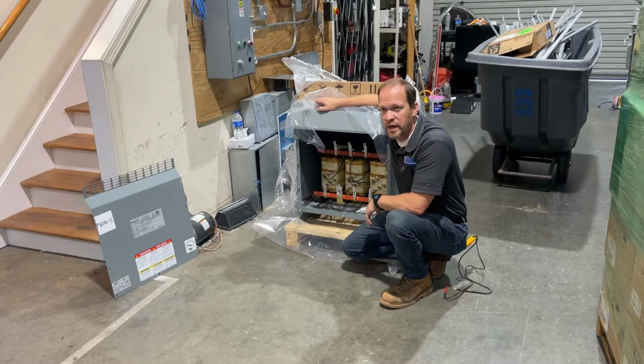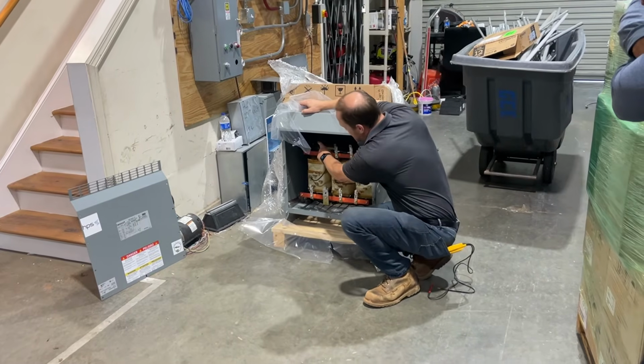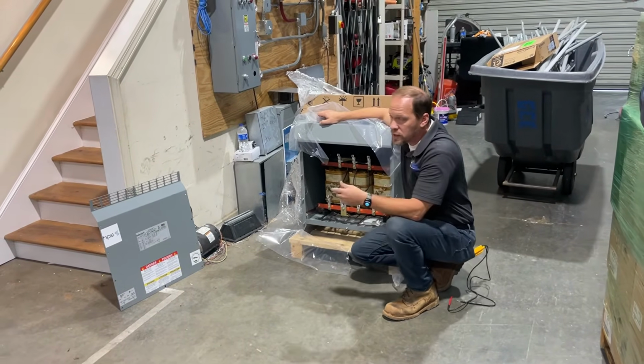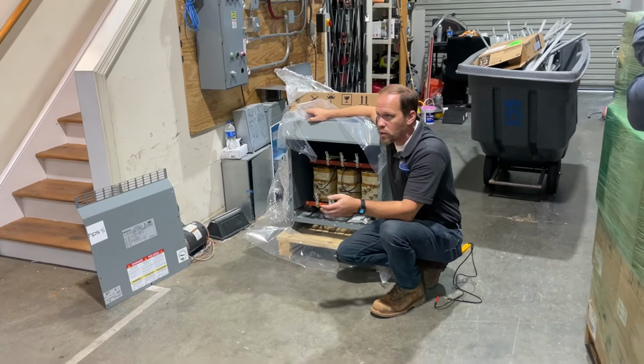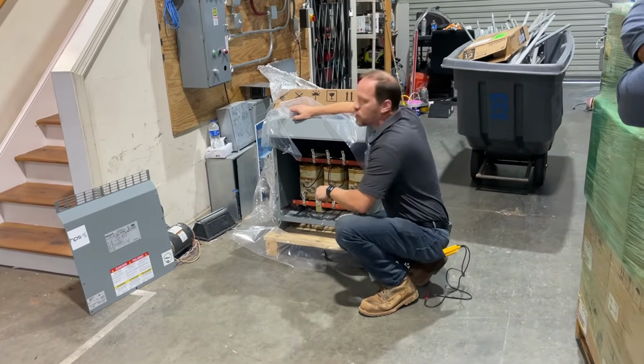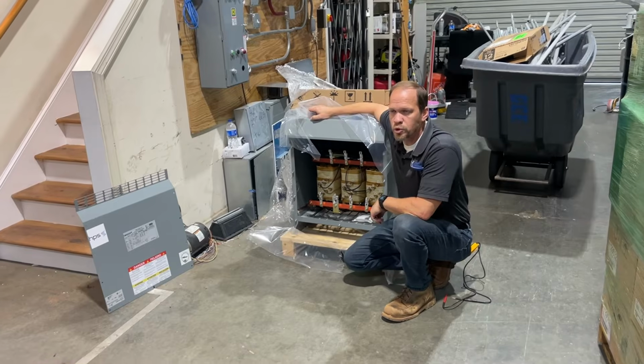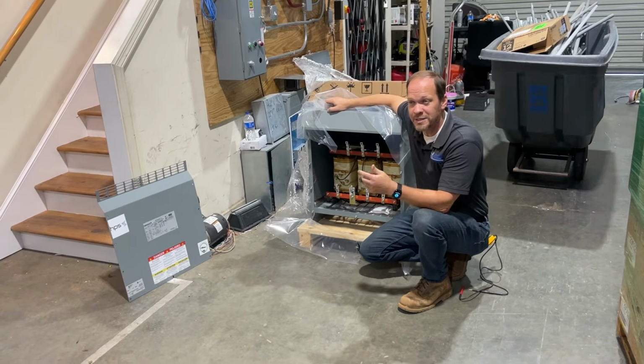Now that's a weird thing, isn't it? You can take that X1 right there, and you can do this in a 480 panel too, or a 480 transformer, and you can take H1 and run it straight to ground, and it won't trip. Ooh-wee, yeah, it's a scary thing.